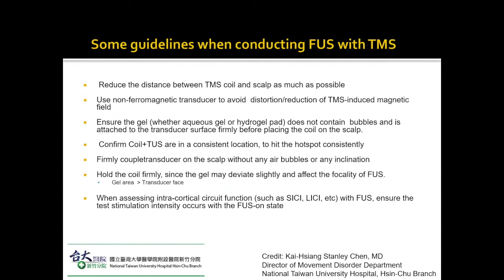Confirm that your coil and ultrasound are in the right location to hit the hot spot consistently. Also be aware that the gel or coupling media may deviate slightly—shifting if it's a solid component, or smearing around if it's a liquid gel. That's something to think about, as it will certainly affect the focality of your FUS testing.